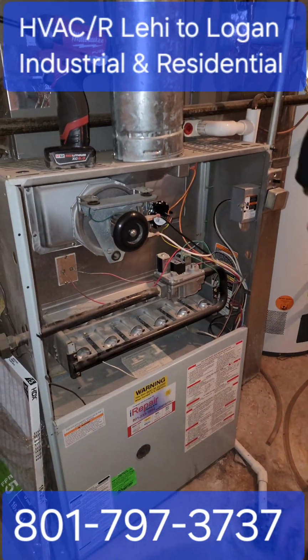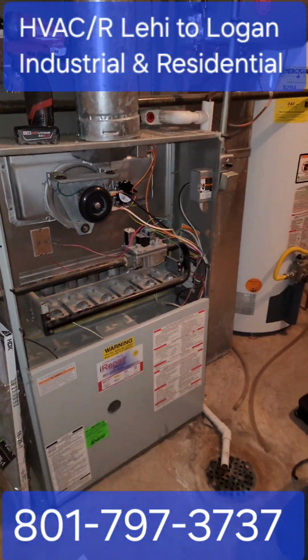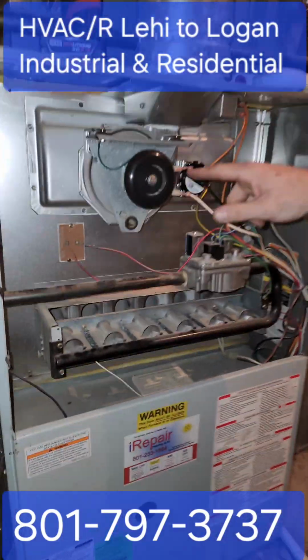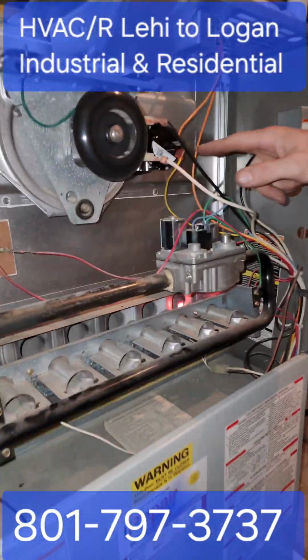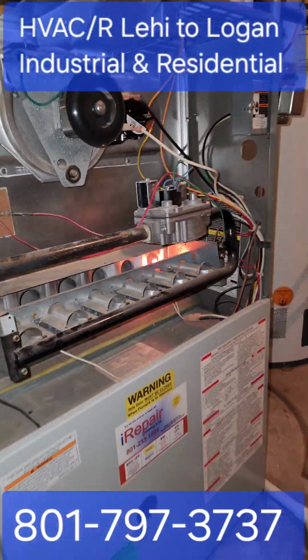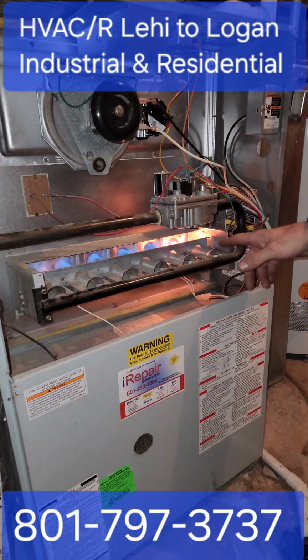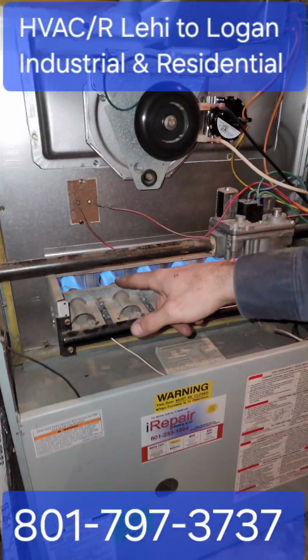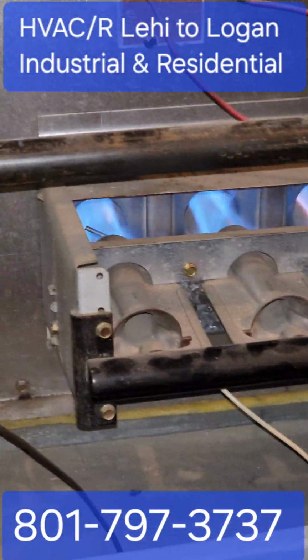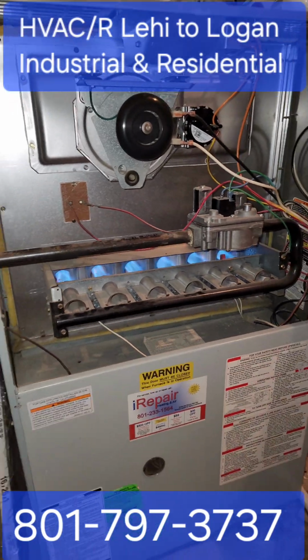So now just watch it. That kicks on. What is that? Spinning wheel? The inducer draft motor. And this is reading the pressure caused by this. So when this kicks on, this switch closes, which tells the igniter that it can light up. It gives that a few seconds to get hot. Once the igniter's hot, gas valve opens. Your flame sensor's on the far side. That senses flame. It gives it a minute to heat the heat exchanger up, then it kicks on the main fan. And then it'll blow heat into the house.